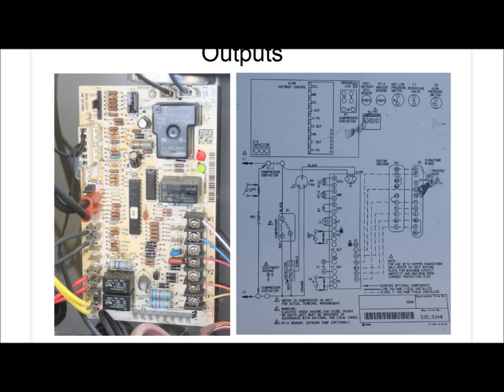So let's first talk about these big black terminals right here. This goes to the reversing valve, and what happens is down here on the O terminal, when we get a 24 volt signal that energizes the reversing valve, it finds its way through the control board and it goes out to the reversing valve to energize that reversing valve.